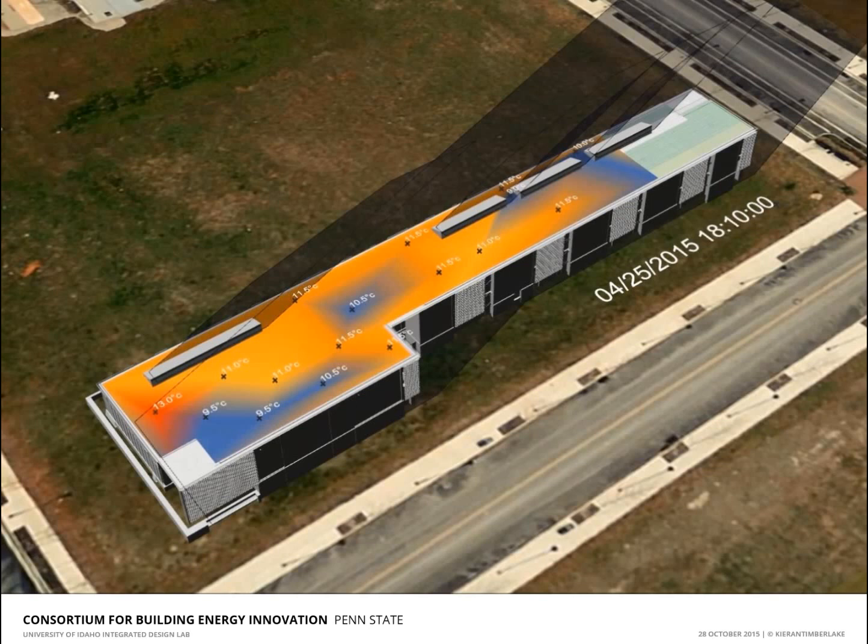We're still able to see thermal variation over the site. We were still able to understand whether or not there's any association between the plantings and what we were actually seeing in the data. And we're also able to use this as a mechanism for determining whether or not there was insulative value in the roof by looking at the temperatures at the roof membrane versus the ambient conditions.